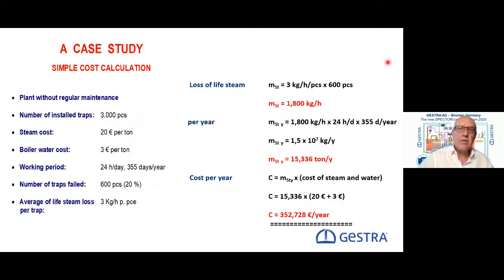So, will we just look for some numbers? If we say we have a plan where we have installed 3,000 steam traps and we make no regular maintenance, we just let the trap run without any work on it. It saves a lot of money from the maintenance. We have the same steam cost, the boiler water cost, the working period should be 355 days a year. We have 20% of failed traps after 3-5 years. That are 600 pieces from 3,000 pieces. The average live steam loss is 3 kilograms per hour per trap.